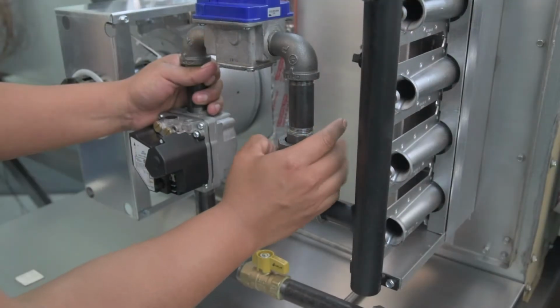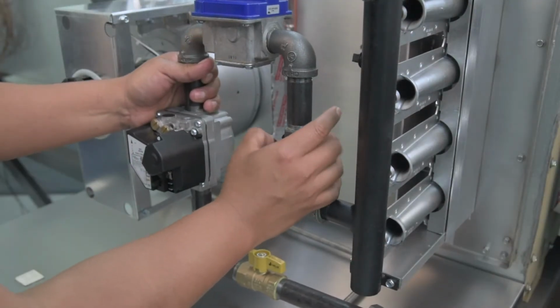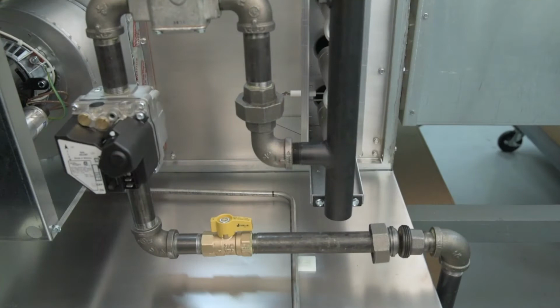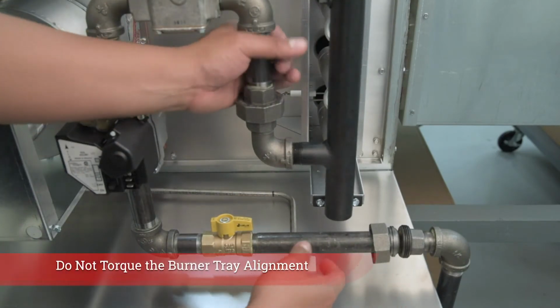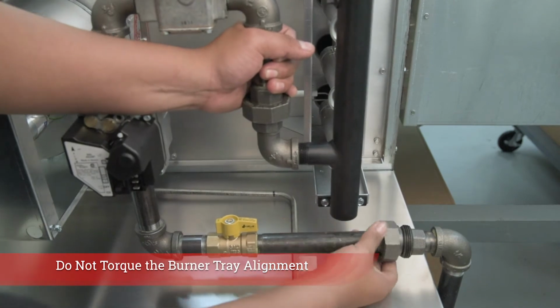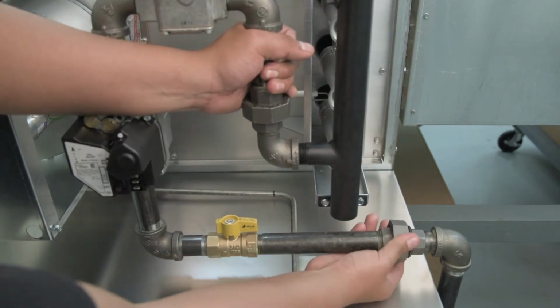All gas trains include unions for easy disassembly for inspections and service. Care should be taken in the field when connecting the gas supply piping to the furnace. Make sure that the supply piping does not torque the burner tray alignment.